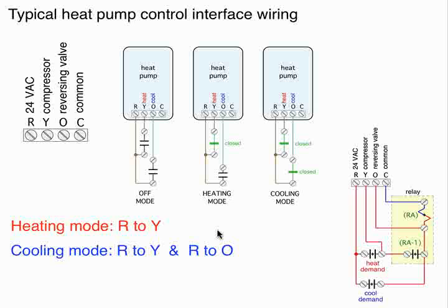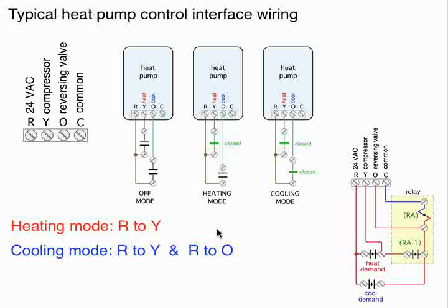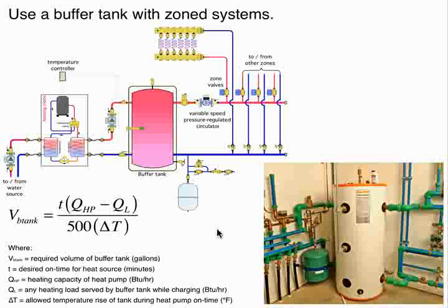Okay, open loop. Hey, John. Yes. A question came in on, speaking of the wiring on a heat pump, in terms of buffer tank sizing. Is there any rule of thumb for how frequently you want that heat pump to cycle on and off in your buffer tank sizing?